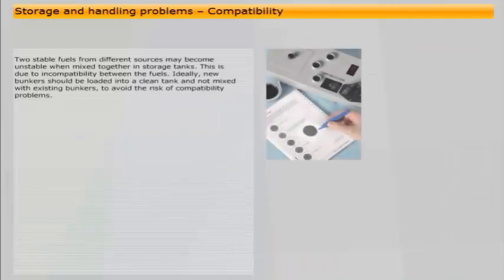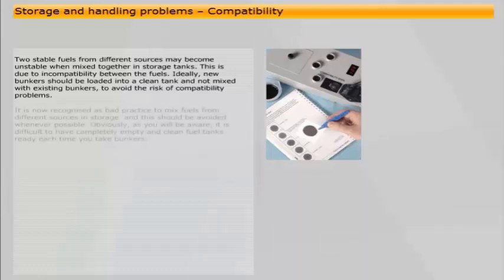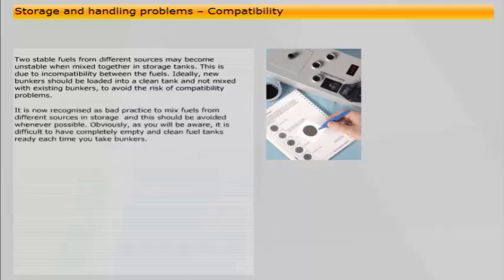Two stable fuels from different sources may become unstable when mixed together in storage tanks. This is due to incompatibility between the fuels. Ideally, new bunkers should be loaded into a clean tank and not mixed with existing bunkers, to avoid the risk of compatibility problems. It is now recognized as bad practice to mix fuels from different sources in storage, and this should be avoided whenever possible.